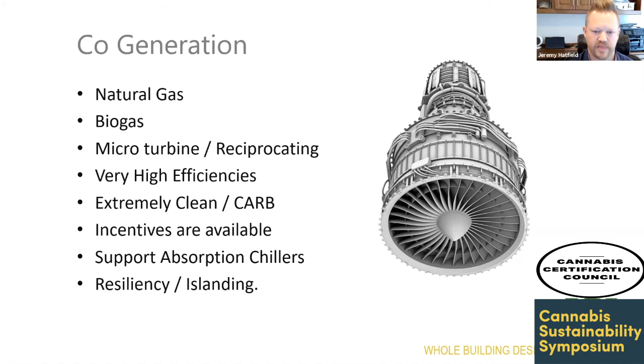If you're doing a hydronic system, you're going to need a lot of hot water for reheat, heat, and dehumidification, so you've got a fairly constant supply. It also adds resiliency to your facility, because you can couple this with the utility source and almost guarantee you're not going to lose power. Just be careful—you've got to have a redundant source for your hot water supply system, because if you switch over to utility power, you're going to lose that heating from your cogen system.